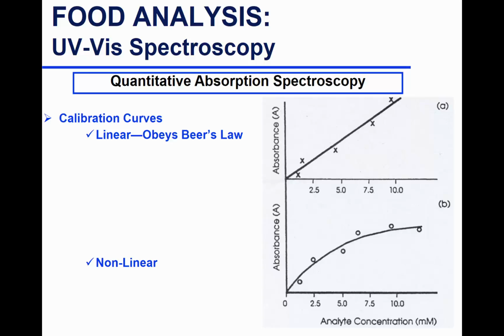Make sure your calibration curve fits all of your data points. You either dilute your standards or your samples to make sure they are within the linear range, and also the threshold. You don't want to dilute too much, or you will lose threshold and become close to the noise, what we call error, which is not true concentration.